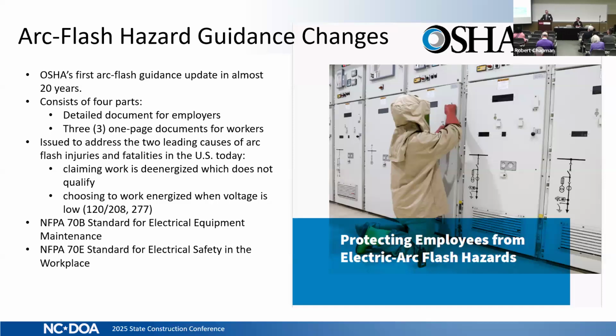And through some research and investigations, OSHA believes the primary causes of why they can't get down to zero are those bulleted items. In interviewing workers, they thought the equipment was de-energized when it actually was not. Or, especially true of older workers who have been doing the same task for decades, they've gotten used to working on low voltage, thinking that low voltage can't injure or kill them. But as you see there, even 120 volts in the right conditions can cause serious injury.